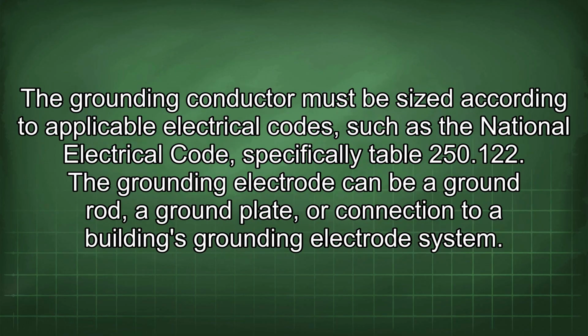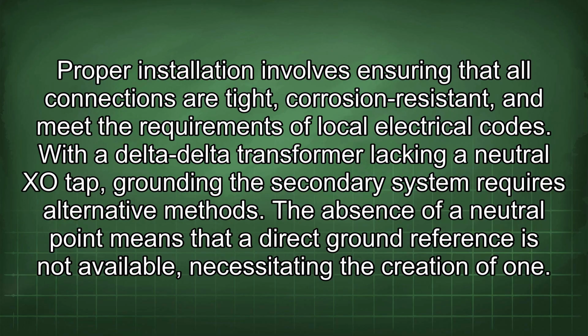The grounding conductor must be sized according to applicable electrical codes, such as the National Electrical Code, specifically Table 250.122. The grounding electrode can be a ground rod, a ground plate, or connection to a building's grounding electrode system. Proper installation involves ensuring that all connections are tight, corrosion-resistant, and meet the requirements of local electrical codes. With a delta-delta transformer lacking a neutral X0 tap, grounding the secondary system requires alternative methods. The absence of a neutral point means that a direct ground reference is not available, necessitating the creation of one.